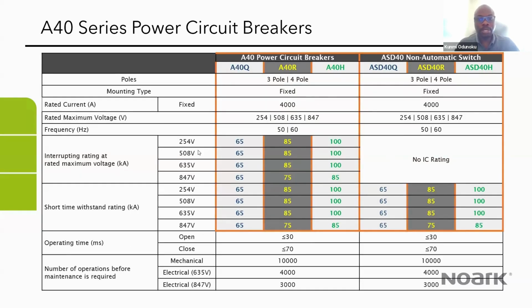For the A40, the only difference is that it goes up to 800 volts. For now, we have only the fixed version for the A40, and the frame size is 4,000 amps. Of course, at 800 volts, the interrupting capacity is slightly reduced. So it's 65, 75, and 85 kA, as compared to the 600 volt rating. It's simple: at 800 volts, you need a more rigid and more robust construction that can interrupt that level of voltage. That's why the interrupting capacity is slightly reduced.